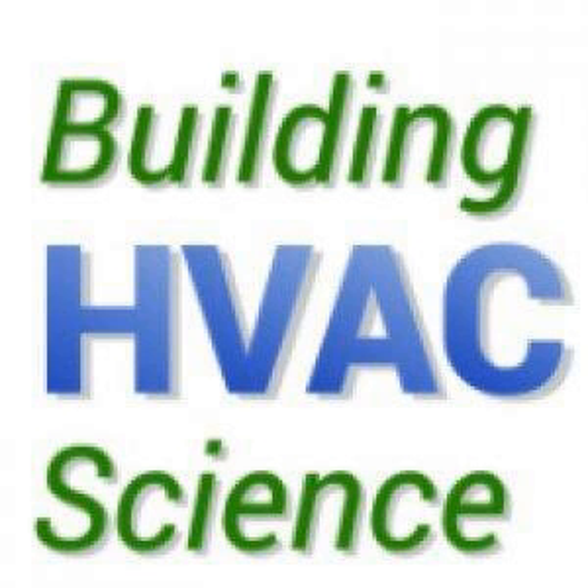So let's take Dayton, Ohio, for example. It's IECC Climate Zone 5, I think. So I took a bunch of seals from Climate Zone 5, gave an initial and a final, and calculated the distribution efficiency, initial and final. Basically, a reduction in distribution efficiency is that unit running longer. So if it's at 60%, it's only getting 60% of the energy where you want it. It's going to run way, way longer. By sealing it, we increase that up to, call it, 83%. So we're getting more energy where we want it, it has to run less, and it's using less energy overall.